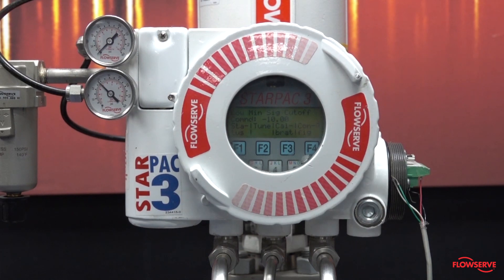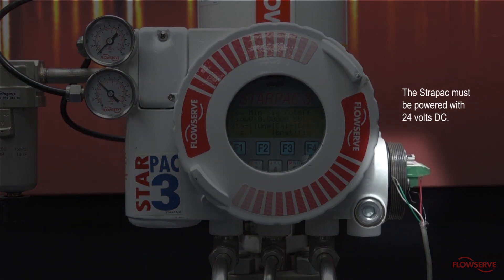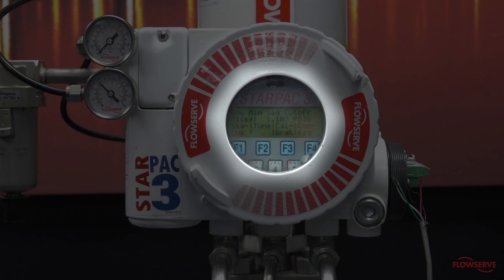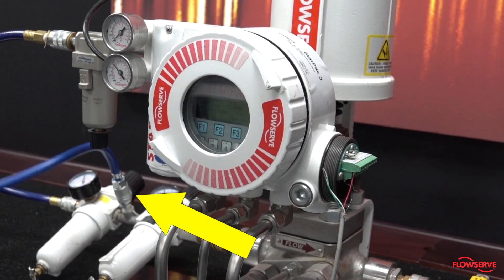This video shows how to perform stroke calibration and actuator pressure sensor calibration on StarPac 3 products using the keypad. The StarPac must be powered and the LCD display must be illuminated before you begin. Instrument air must also be supplied.